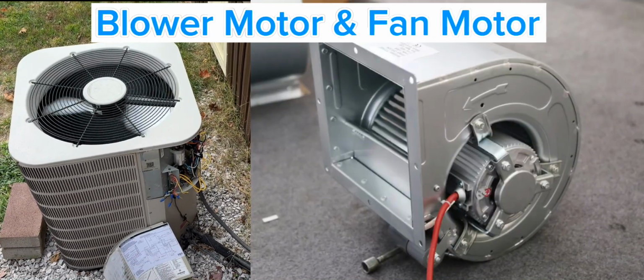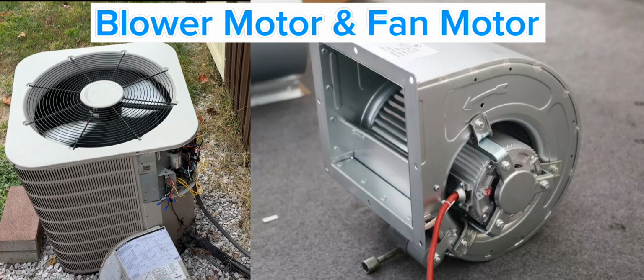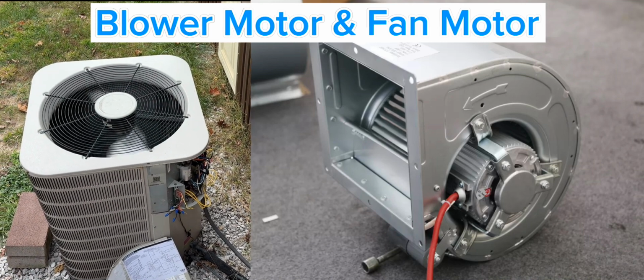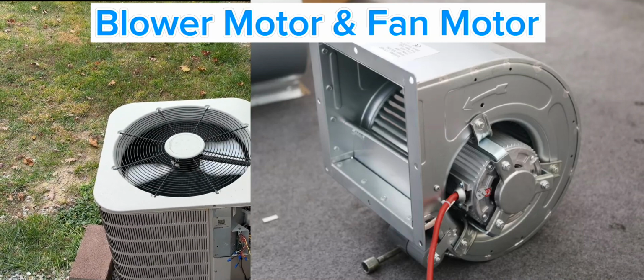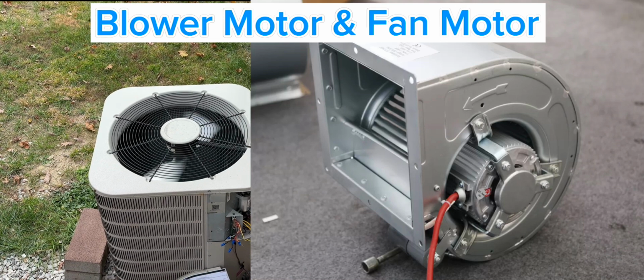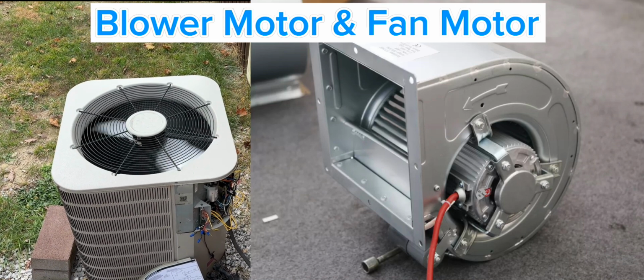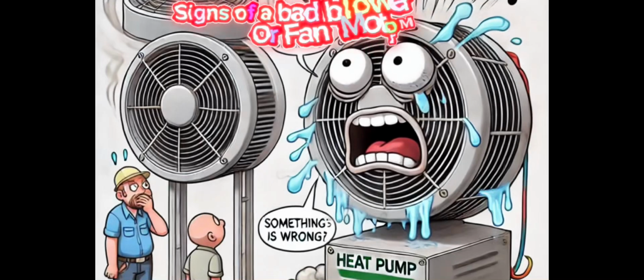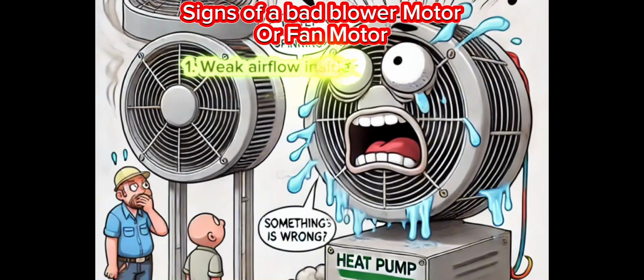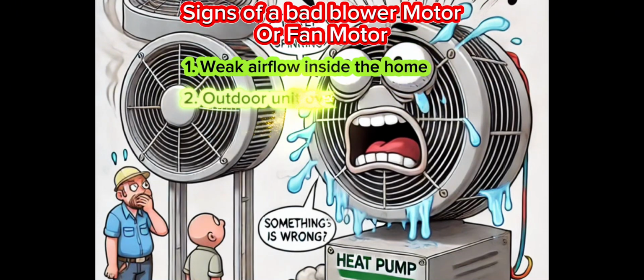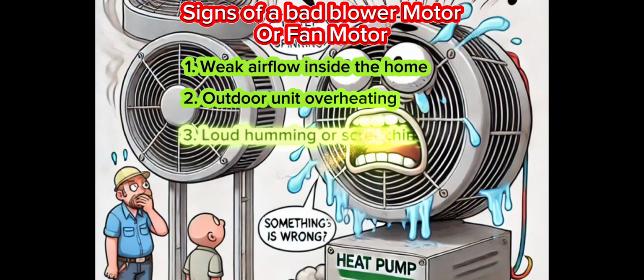A heat pump moves air using two key motors: the blower inside your air handler and the condenser fan motor in the outdoor unit. If either fails, your system won't be able to circulate air properly. A failing blower motor means weak or no airflow indoors, while a bad condenser fan motor causes the outdoor unit to overheat and shut down.